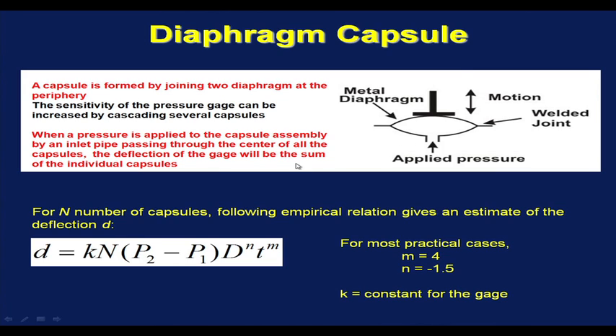When a pressure is applied to the capsule assembly by an inlet pipe passing through the center of all the capsules, the deflection of the gauge will be the sum of the individual capsules. One such capsule is shown here. Imagine several such capsules are stacked and this inlet pipe passes through the center of all the capsules. Then the pressure applied through the inlet pipe will cause a very large deflection of the pressure gauge. So, we can increase the sensitivity of the pressure gauge substantially.